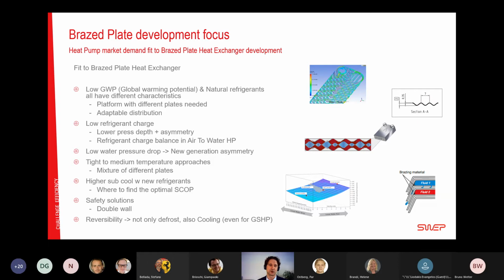low water pressure drop. Because of the new eco design in the EU, but we also see this in APAC very importantly, where we need to still have a very high heat transfer, but lowering the water pressure drop. And that is a new balance, and it needed a new development of the asymmetry in the current heat exchangers. We have a mixture of plates to manage either tight or medium temperature approaches on the heat pumps to manage the required COPs.